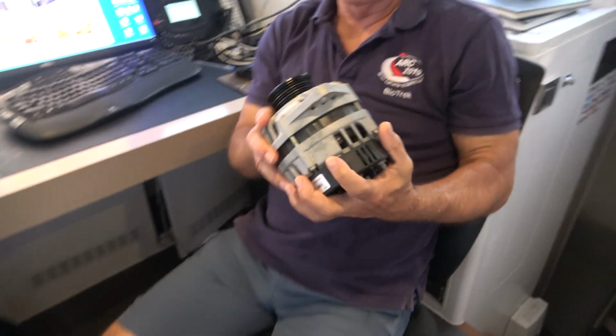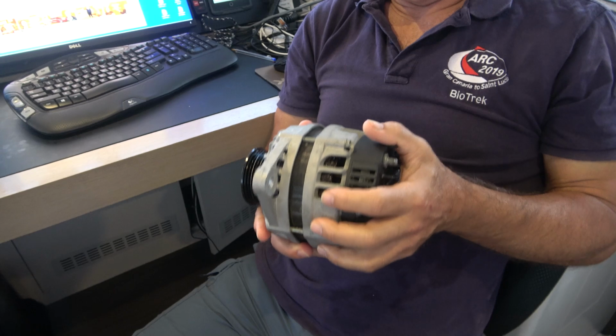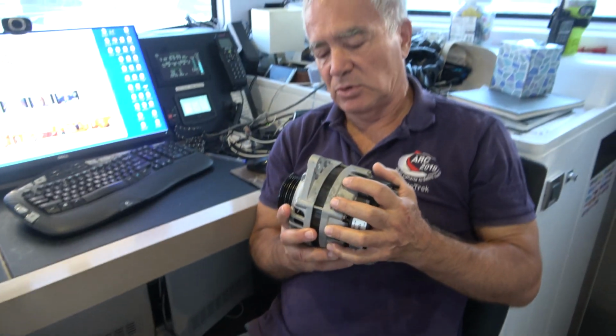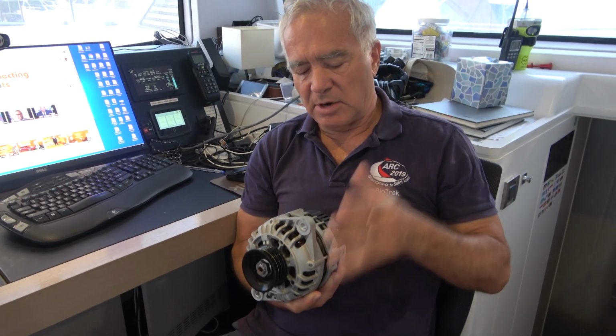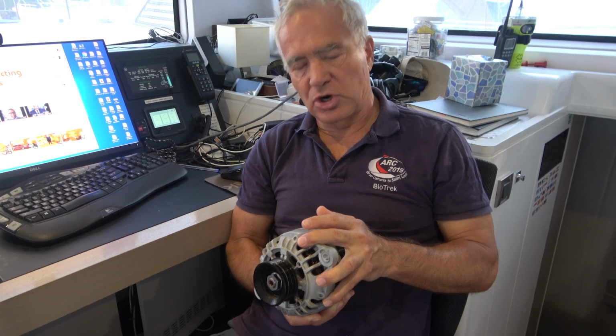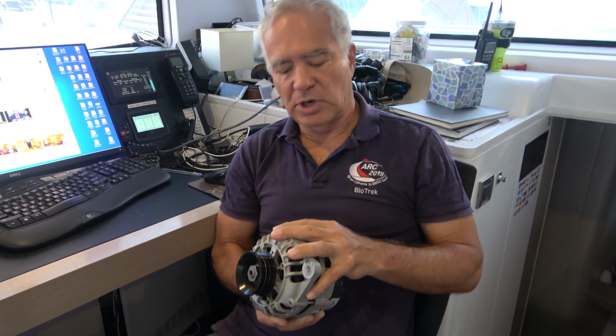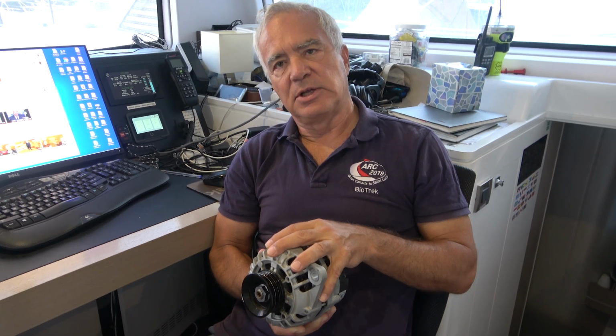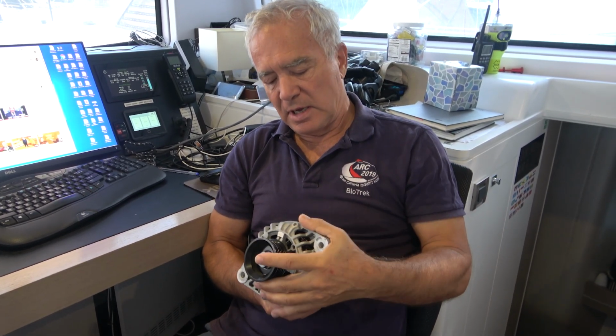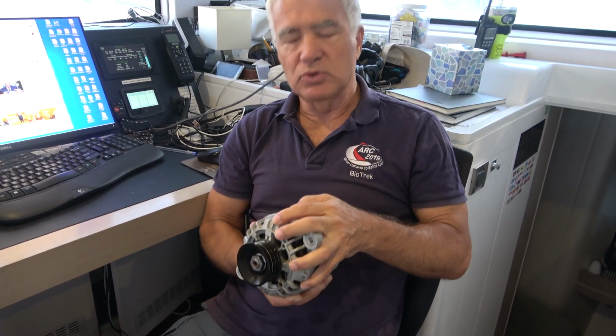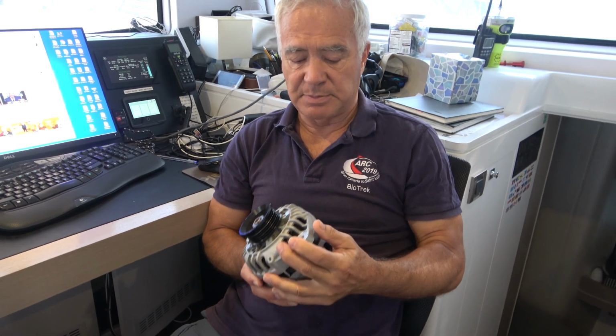So I always said if the generator fails, because we only use the generator to charge the batteries anyway, we have the inverters, and then we can just use the engines. But the engine alternators that we have on it are these guys, 28 volt, 60 amp alternator, which in theory isn't too bad - 60 amps is still about 1 kilowatt. The problem is they're built for cars, and they'll charge a car battery, which is only used to start the motor, and that's it. So they'll be able to produce their output for a few minutes, and then they just derate because they get too hot very quickly. So they cannot be used to charge a large battery bank, especially a lithium-ion battery bank.